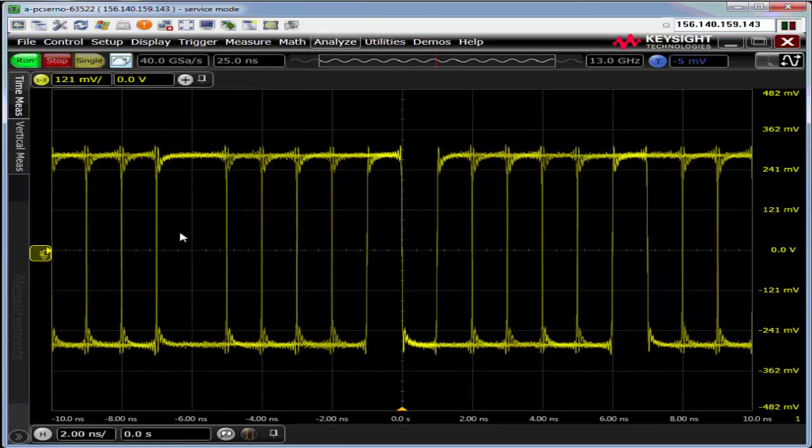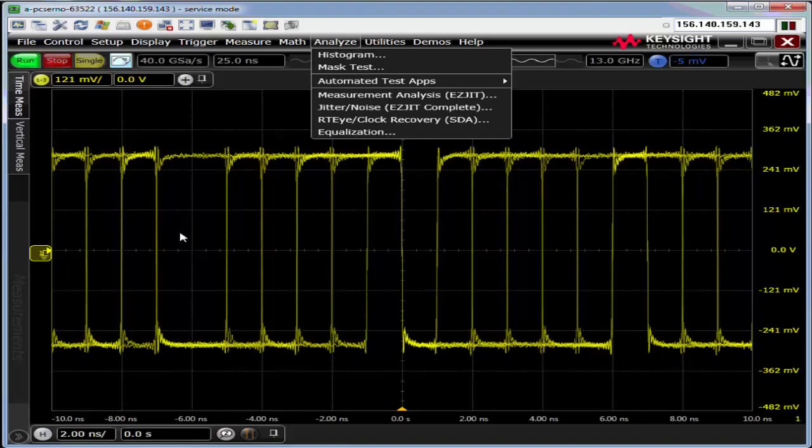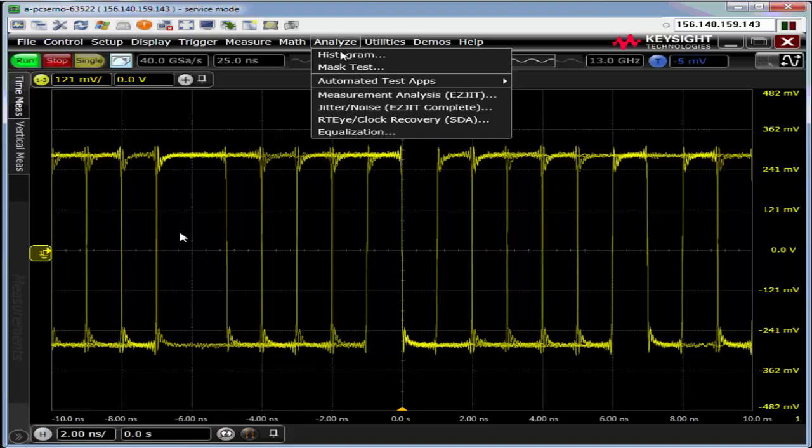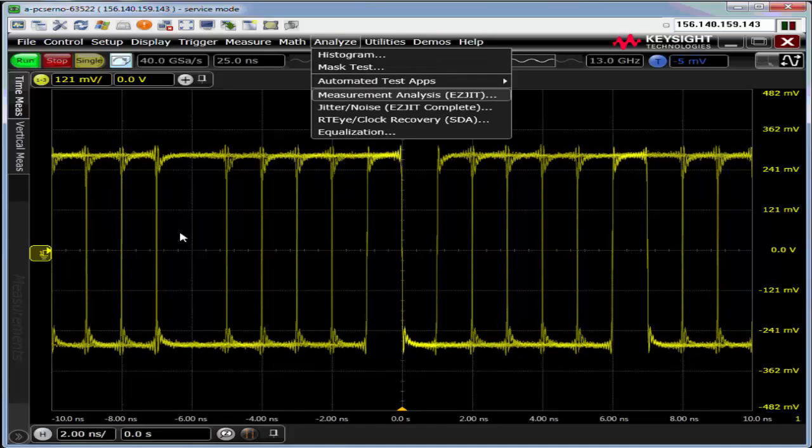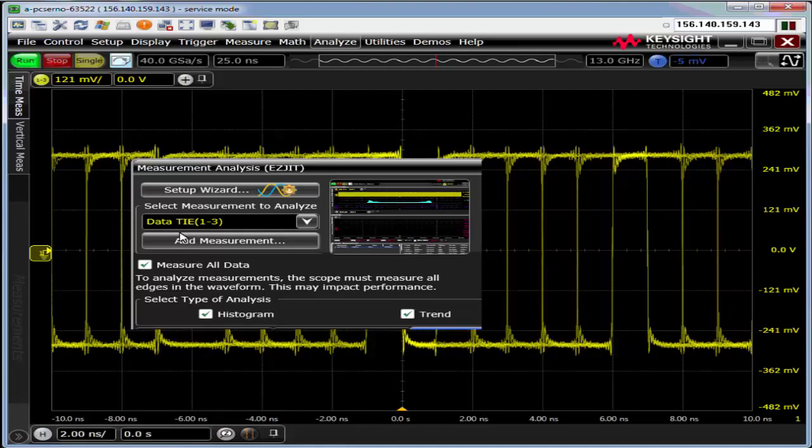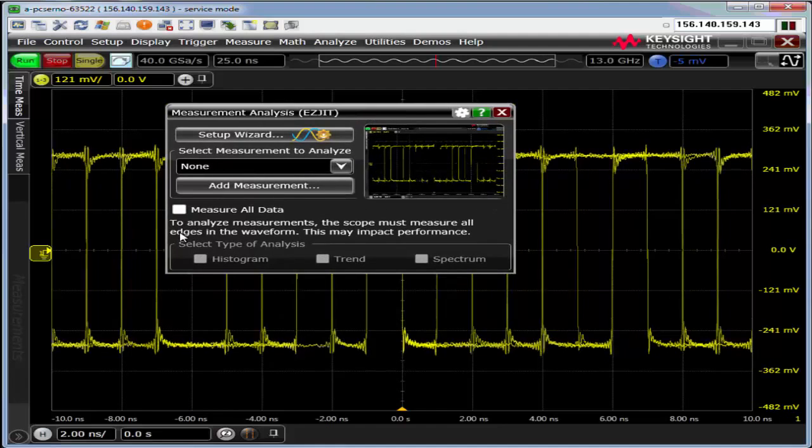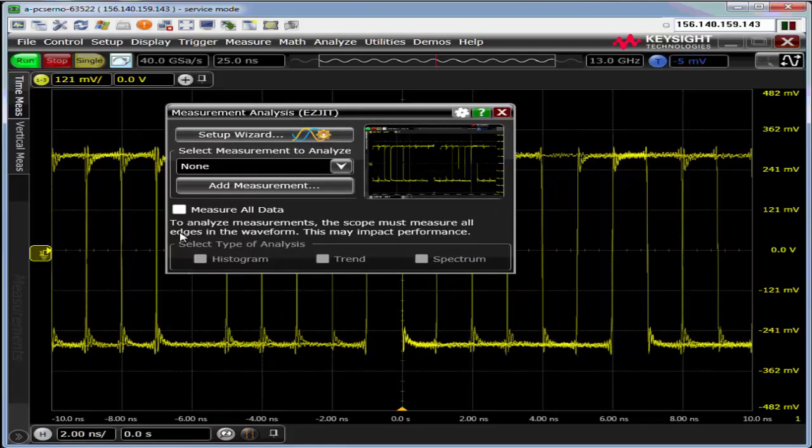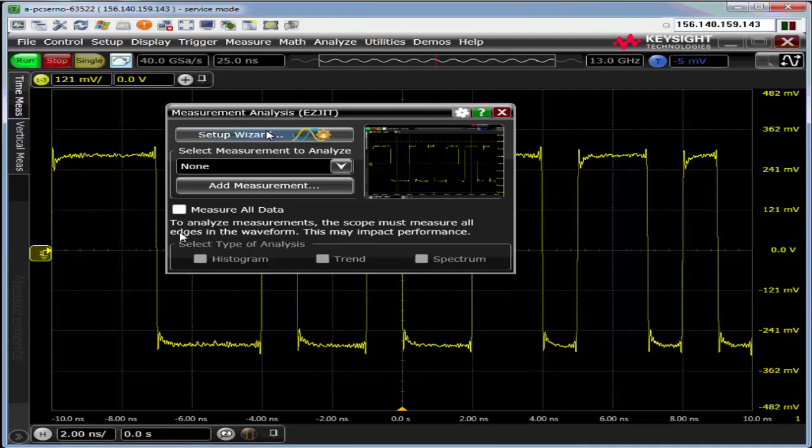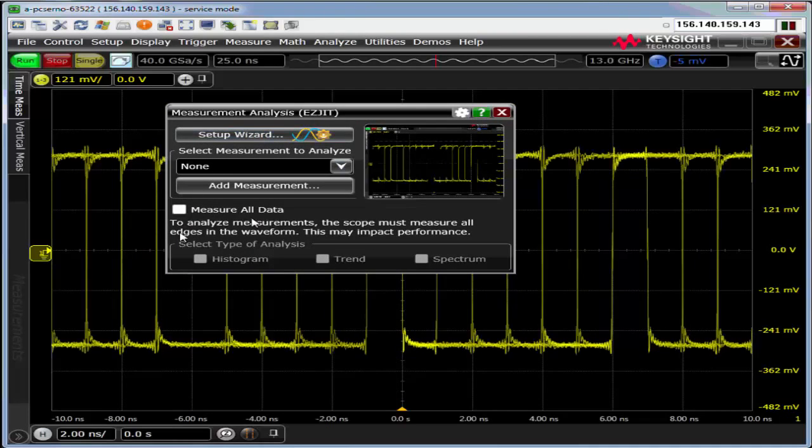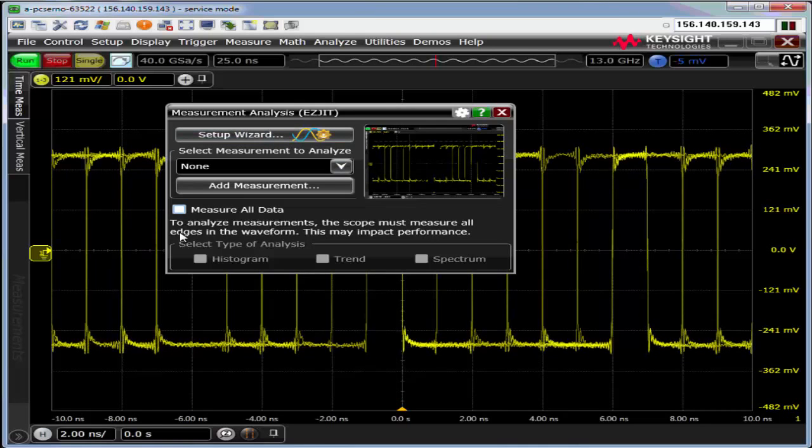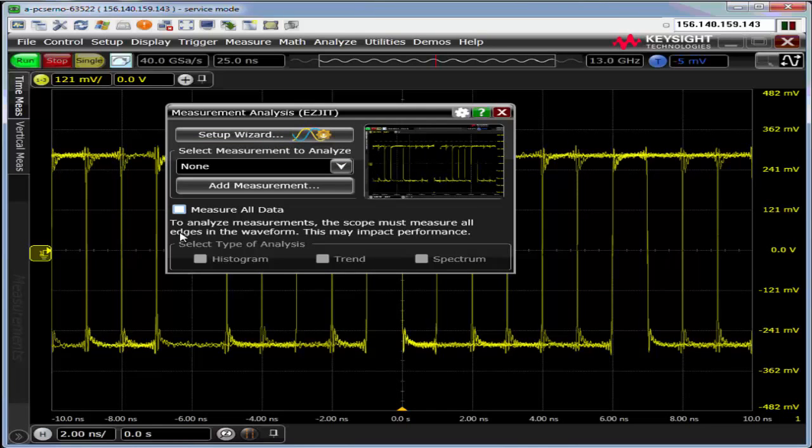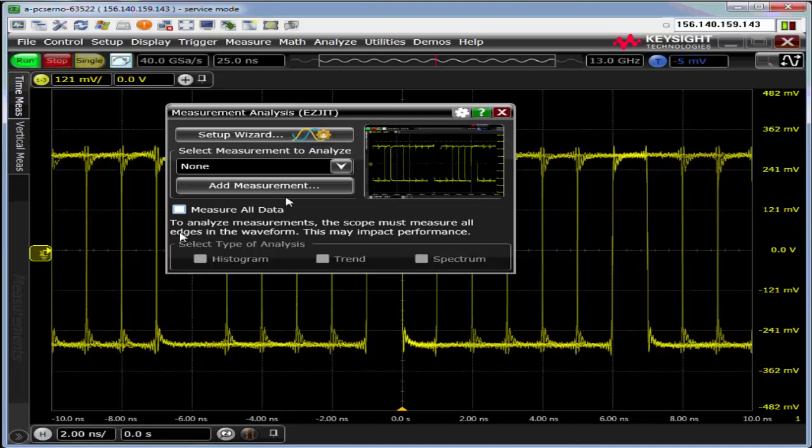To go through the Jitter wizard, let me go to the Analyze drop-down and select Measurement Analysis EasyJitter. There are two ways to do this. One is to use the setup wizard or basically turning on all measurement, measure all edges, which essentially turns on jitter mode.